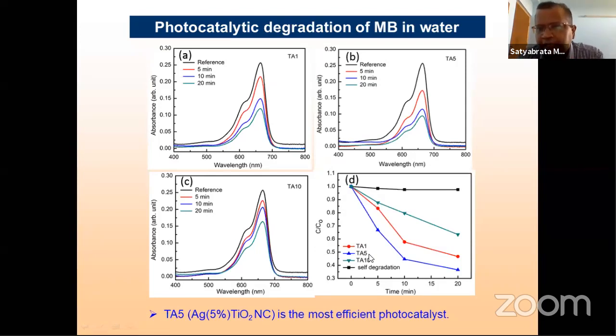When you record UV-visible spectroscopy, you want to look at absorbance. Absorbance depends on the concentration of molecules, if you are looking at a solution, in the liquid phase. When you vary the concentration of various molecules or analytes, the absorbance is a linear curve. As you increase the concentration, the absorbance will increase. You can record up to an absorbance of around four in various UV-visible spectrophotometers.